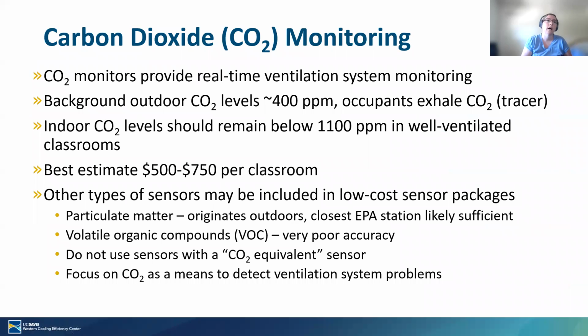So I want to talk about carbon dioxide monitoring. The test adjust and air balance report essentially gets the ventilation set up at one moment in time, right? And generally speaking, it should persist, right? But if maintenance staff unknowingly adjust it, if a mechanical component fails, if the filter gets really clogged, if something happens along the way, the question is, how would we know, right? Because that might have been a year since that system was tested.